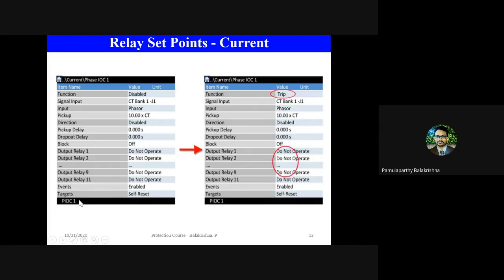Then you have something known as events, meaning whether the relay has to record events, like how many times this overcurrent function has triggered, or how many times the current has reached a particular level. All those things you can record as events for postmortem analysis. And targets means all the messages or records that you have recorded, whether they need to be self reset after some point of time, or you can keep them so that unless the operator sees them and then resets them, they are not cleared. Self reset means the relay itself will reset the information or the memory because it has a shortage of memory after some point of time. But otherwise, if you do not keep self reset, the operator has to manually clean the files which are there in the relay.